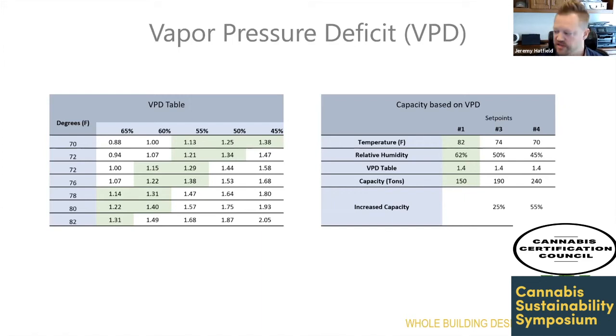Another important thing to note: as we raise things, let's fix our VPD around 1.4. I've heard some growers go as low as 0.8 VPD, and some as high as 1.5. We're going to pick 1.4 in this scenario. And if you were able to accept 80 or 82 degrees Fahrenheit in that grow area, you'd be roughly 55% lower than a grow room that wants 70 degrees.